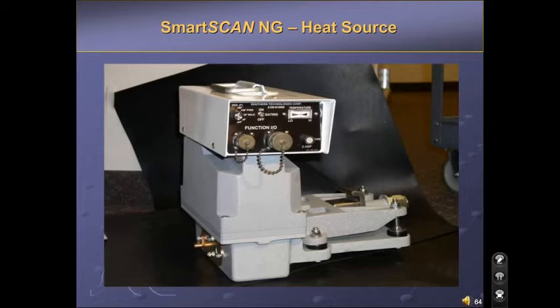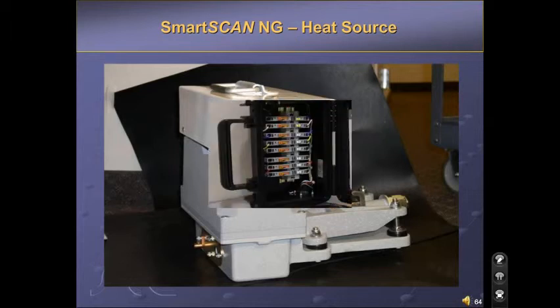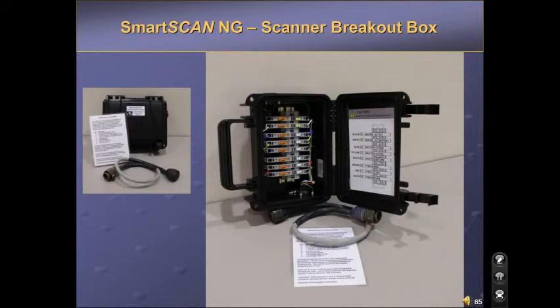In extreme temperatures, whether hot or cold, always make sure the heat source is at the proper temperature level before starting AutoCal. The 2300-970 scanner breakout box is designed to be connected between the scanner and the detector to facilitate measurement of scanner signals. With the supplied adapter cable, the breakout box can be connected at the detector end or the scanner end of the scanner cable.